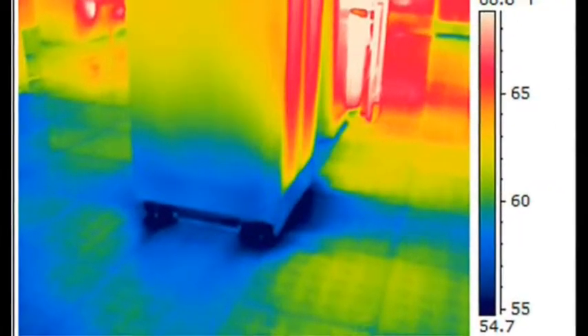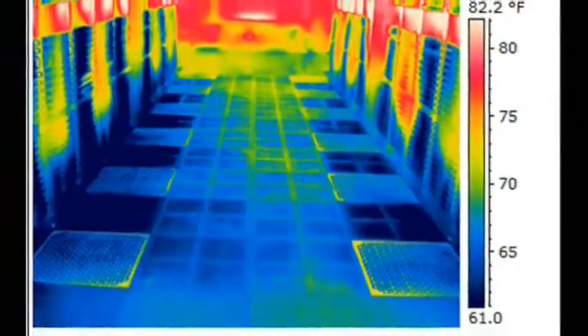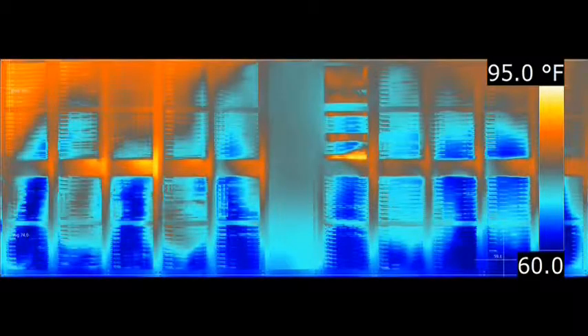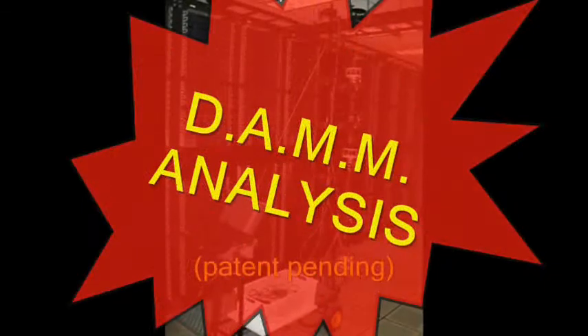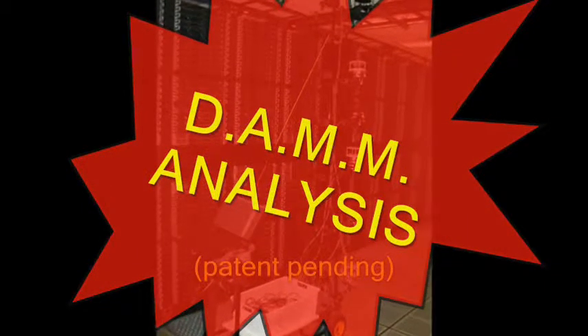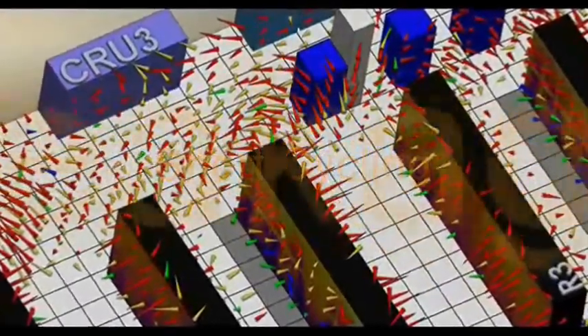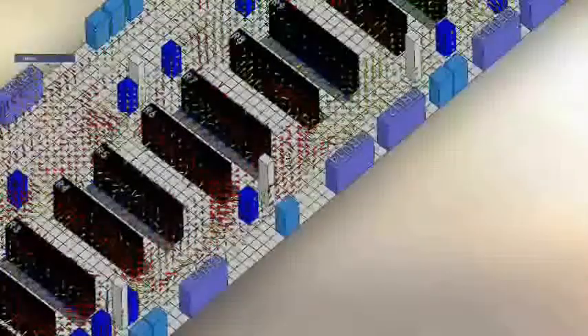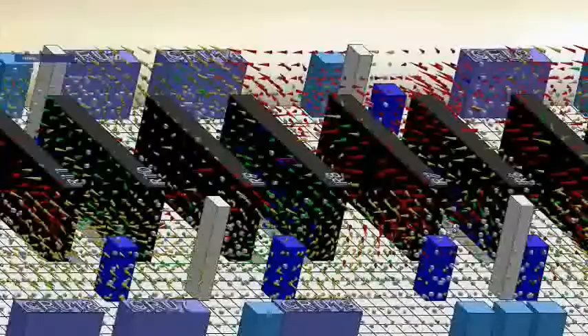return on investment. What sets our service apart from others is the way in which we collect, process, and present data. By coupling panoramic infrared images with air velocity, temperature, and humidity readings from our patent-pending data center airflow measurement and mapping tool, we quickly and easily identify undesirable airflow patterns that are actually occurring in the data center. We display results graphically using computer-aided design software, and we also generate cooling quality metrics from both DAMM tool and infrared measurements.